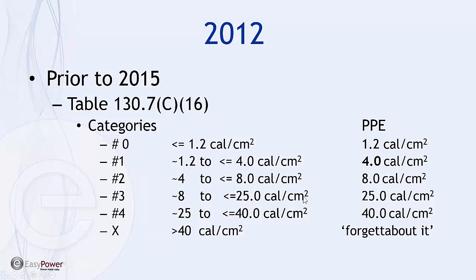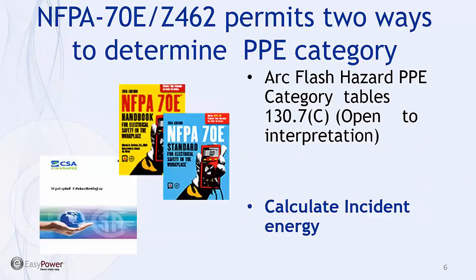The downside, at least at that time, was that we were oversuiting, to be conservative. But this is a fairly wide range of incident energy, and it came out as cross purposes between trying to meet a level of safety and making the job more difficult. This type of suit, or even more so when rated for 4 calories, was cumbersome, made the work more difficult, reduced dexterity, was very hot, and in some cases made a dangerous situation worse because it reduced visibility and limited what people could do. So the feedback was it was onerous and made things more difficult.